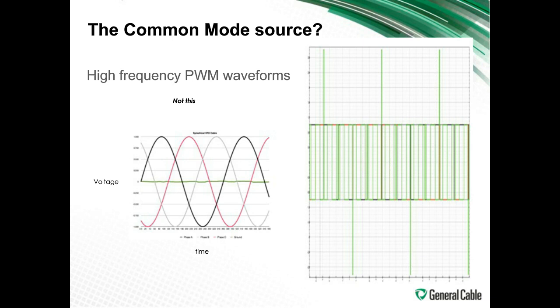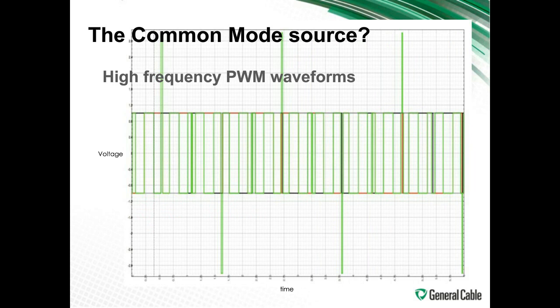And in the process of doing this with the high frequency and rapid rise times, what we're seeing is that the peak voltage actually has voltage on top of voltage. It's a phenomenon that creates extra voltage that is not seen in normal 60 hertz waveforms. So this high frequency can cause trouble because you're having more standing waves over time at a higher voltage than needed, or than what you account for.